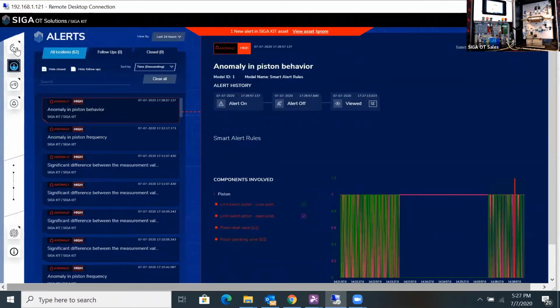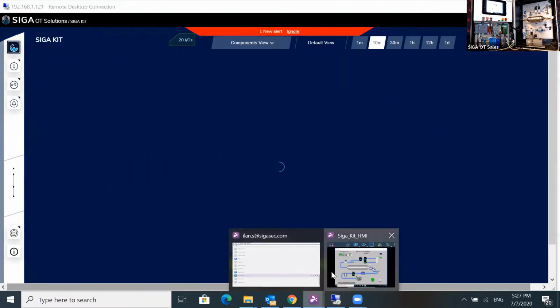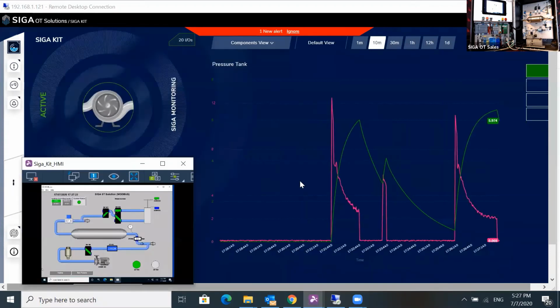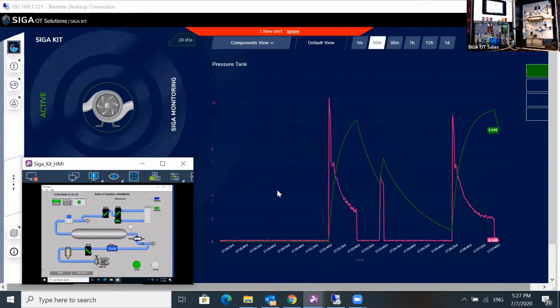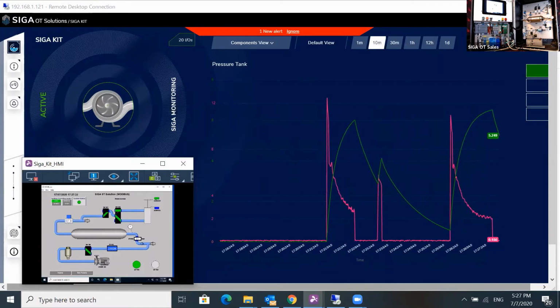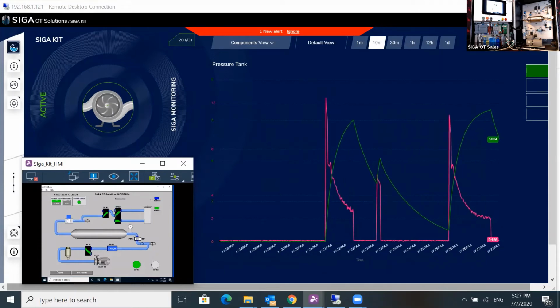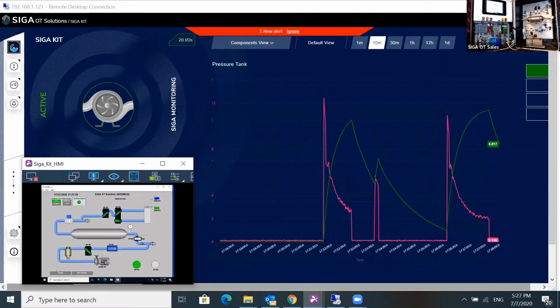The second scenario simulates a cyber attack to the level 1 layer, which means someone was able to infiltrate and take control of the PLC and change the set points controlling the process without any indication to the operators at the HMI level. This is a common and dangerous cyber attack for ICS networks. In this scenario, the operator is not aware of the potential occurrence of such an event. Hence, he has not pre-configured it up front.